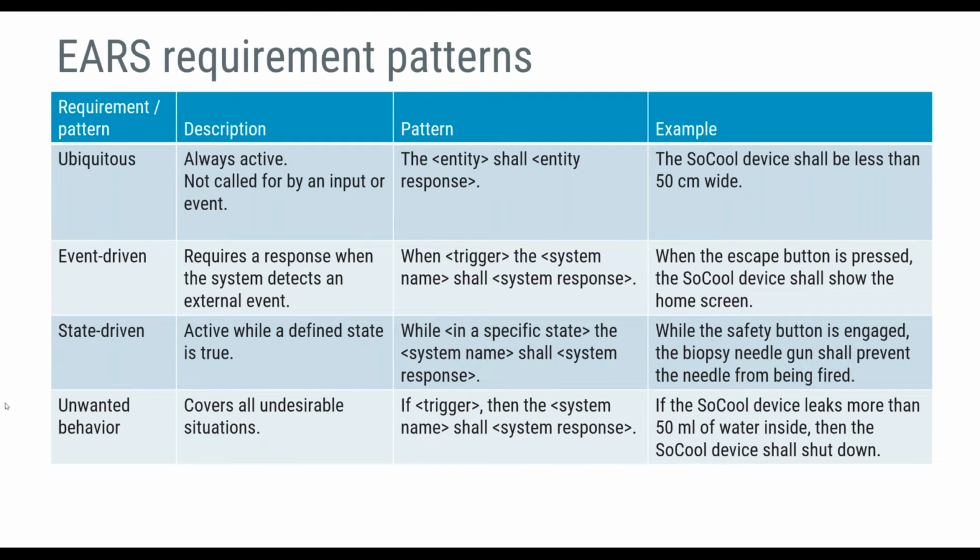Again, actually, it's quite useful because in some cases where you write the requirements really properly for an embedded software or software as a medical device, you can actually use the requirements almost like a framework for the code. So that's super useful. So I said that it's useful in all cases, particularly in software products. So keep that in mind.